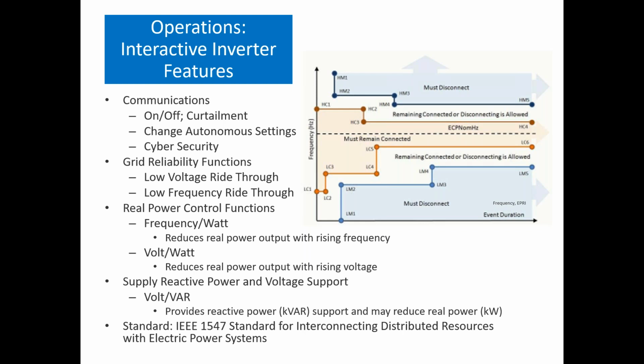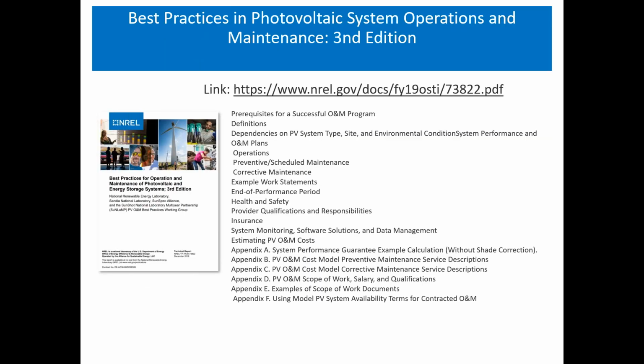Cybersecurity is another hot topic. Basically, a lot of these platforms are predicated on the assumption that I'll just be able to take that blue Ethernet cable from my facility network and plug it into the inverter. That is proving to be generally not the case. And so some kind of separate data backhaul and communications might be required. We can't assume that we can use the site network even in a commercial or residential application.